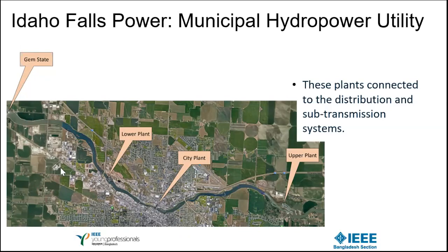So the key point here is run-of-river hydropower plants, because it's a low-head operation and it is being operated by the Kaplan turbine. Because of its mechanical design in nature, it starts showing some instability when connecting to the local load. Say, for example, if you have a 10 MVA run-of-river hydropower plant, the ideal is that it should support 10 megawatt of load, right? Say you re-energize the distribution feeder, you identified the critical load, and you started to reconnect the critical load. You connected 1 megawatt, then 2 megawatt, 3 megawatt. So you are stepping up the load.